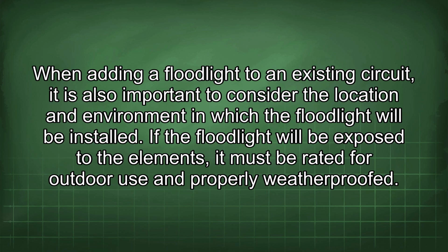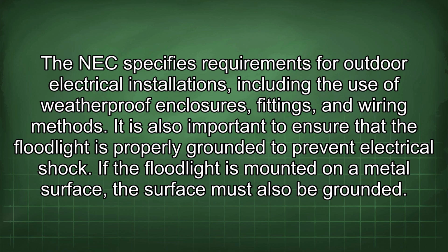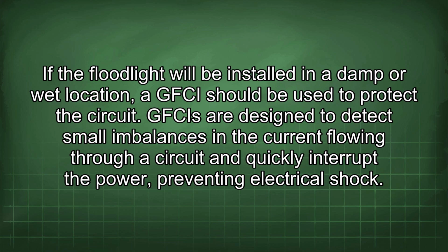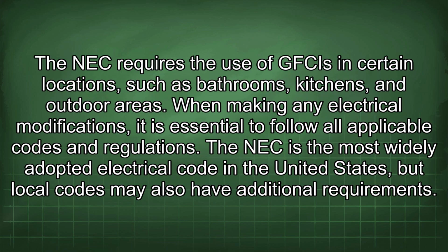When adding a floodlight to an existing circuit, it is also important to consider the location and environment in which the floodlight will be installed. If the floodlight will be exposed to the elements, it must be rated for outdoor use and properly weatherproofed. The NEC specifies requirements for outdoor electrical installations, including the use of weatherproof enclosures, fittings, and wiring methods. It is also important to ensure that the floodlight is properly grounded to prevent electrical shock. If the floodlight is mounted on a metal surface, the surface must also be grounded. If the floodlight will be installed in a damp or wet location, a GFCI should be used to protect the circuit. GFCIs are designed to detect small imbalances in the current flowing through a circuit and quickly interrupt the power, preventing electrical shock. The NEC requires the use of GFCIs in certain locations such as bathrooms, kitchens, and outdoor areas.